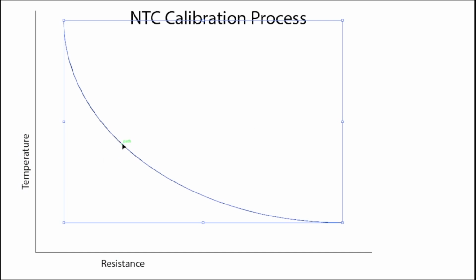Now, when you buy an NTC probe, it comes with a curve already, published by the manufacturer of the probe itself, and that's what you generally go off. But NTC probes can have a little bit of error in there, but if you do this calibration process well, you can actually get very good and accurate, reliable results with an NTC probe.